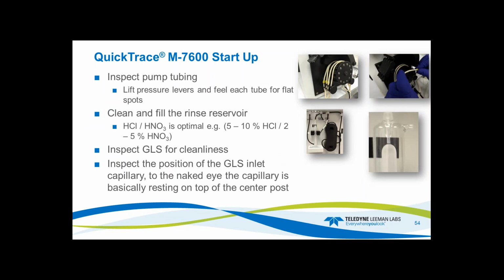Now, so quick trace startup. So this is really fast. You inspect the pump tubing, lift the pressure levers, and feel each one for flat spots. Replace if you need to. Clean, rinse, and fill the rinse reservoir. I recommend, for PPB analysis, HCl, nitric acid rinse, maybe like a 2%, 5% is similar. It's a really pretty forgiving system, so you don't have to sweat it.